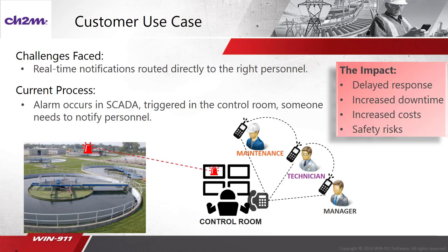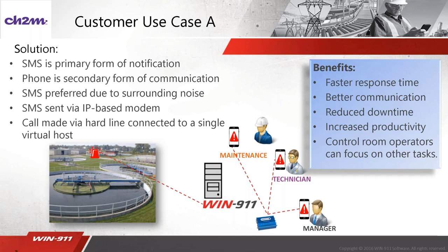Now we're going to get into our first use case. Yuri is going to take us into a deeper dive into a project where he specifically used WIN-911 at a water and wastewater facility. For Use Case A, this is an example of a customer that uses SMS as a primary form of notification and a phone call as a backup. The reason they prefer SMS is due to surrounding noise — operators often don't hear calls, but they definitely check SMS messages often. Additionally, they don't have smartphones, which is another reason they wouldn't currently be open to using the WIN-911 mobile app. The SMS messages themselves are sent via an IP-based modem that sits on the network.